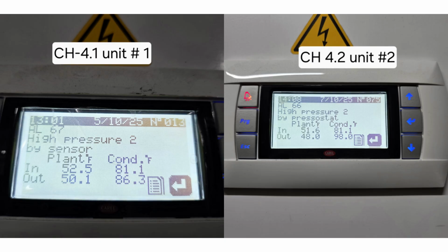Troubleshooting steps: check condenser coil cleanliness and fan operation. For water source units, check water flow rate, strainers, and isolation valves operation. Verify the refrigerant charge, if solenoid valve stuck, and if four-way reversing valve working properly or not. Make sure discharge pressure is within manufacturer limits, usually around 350–450 psi for R410A systems. Reset the alarm only after correcting the cause, not before.